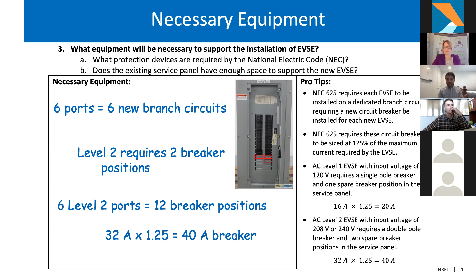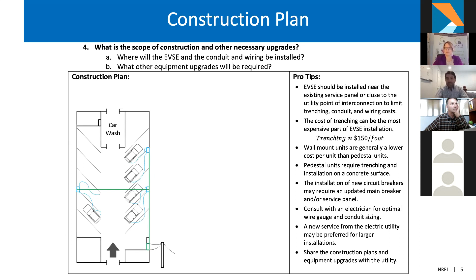No problem at all. The last step, as we mentioned earlier, is the construction plan. So you have your EVSE all set out, you know how much power you'll need and what equipment to install. The next step is looking at the construction plan: planning out the conduit raceway and where the wiring will go. You'll work with your electrician to make sure the wiring sizing is accurate, because wiring selection is a bit of an art form. There's guidance from the NEC, but it's somewhat dependent on the load, length, and voltage. There's a trade-off between wire gauge thickness and how much loss you're willing to accept over the line. So sizing your wiring is something you should definitely work with your electrician on.